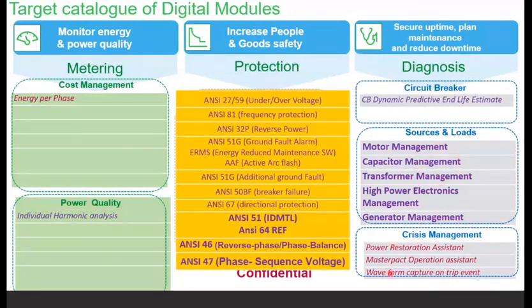A power restoration assistant, operation assistant, waveform capture, predictive life estimate, all these digital modules will be available in store. So you can select these digital modules at the initial phase also, while ordering the breaker. You can ask us that I want this breaker with all these digital modules. The breaker will come by default loaded with all the selected digital modules, or again at a later stage, after commissioning or at the panel builder shop floor, if your features have changed, then you can upgrade the breaker. A service person will come to your place and upgrade the breaker by downloading the digital module.